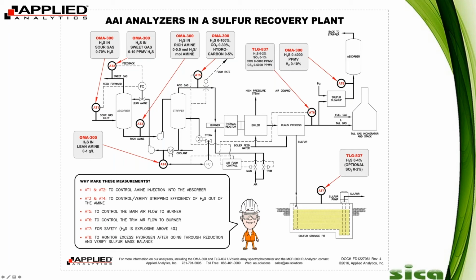So another application in an SRU, and the only other application where we use the TLG, is in the sulfur pit. So what are you supposed to do with all the liquid sulfur that you've converted and collected in your condensers? What most people do is they store it in a giant concrete pit. They keep the pit at a high temperature to allow the dissolved gases to come off. And what we do is we measure in the headspace of that pit. We measure H2S in the headspace to ensure that it never reaches its lower explosive limit.